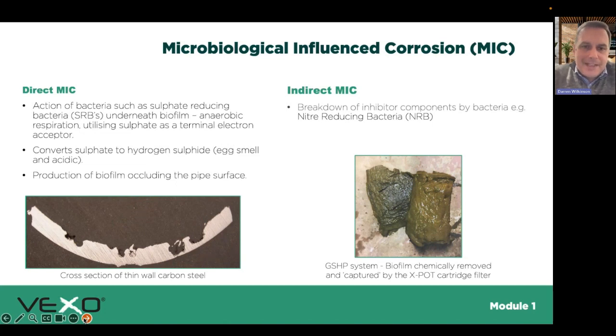So essentially we can have bacteria. If you imagine the fresh water that makes up to the closed loop system, pipework can be sitting there for some time before there's a demand on the system that says it's only topping up. And in that time, mains water will have a very low total viable count. It has a low level of bacteria in the water. Typically, we like to think, certainly not any pathogenic concerns, but certainly low levels of bacteria. And of course, if it sits there idle and it's got the right temperature, it's going to proliferate. So every time the system makes up, you run the risk of giving it a flu almost, giving it a dose of this bacteria. Once it's into the system under stagnant conditions, it will multiply.